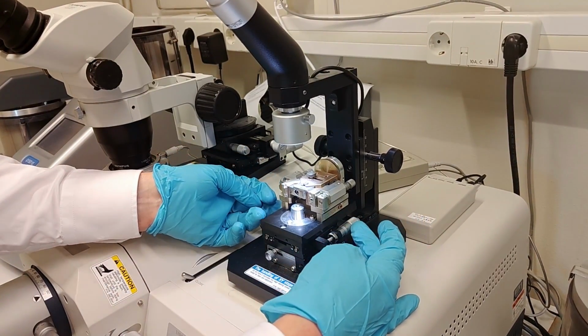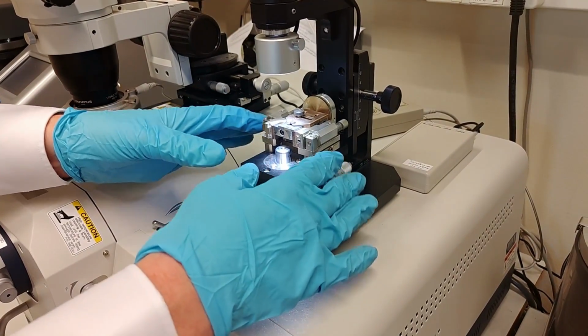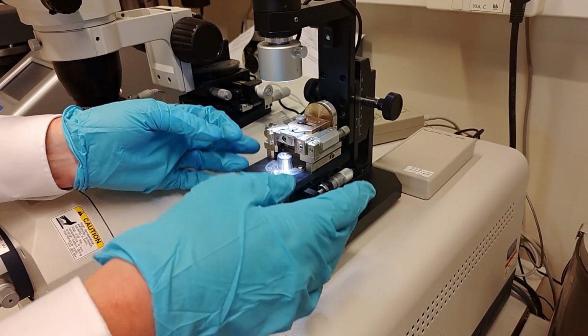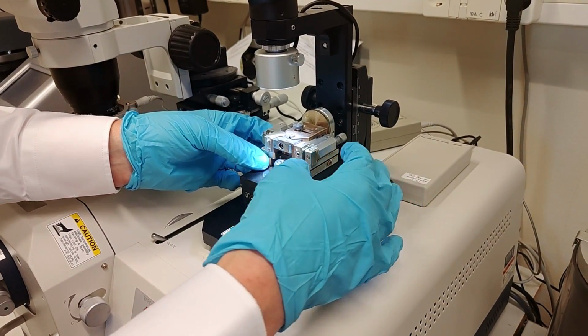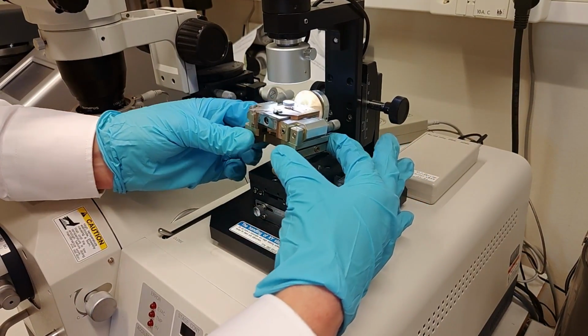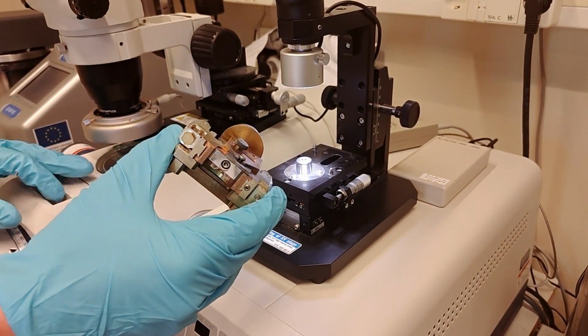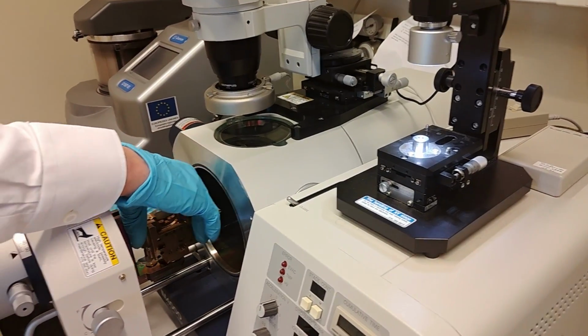These two screws on the bottom here, you should never touch. They are for calibration of the beam versus the whole thing here, so no users should play with this. So when I want to move this, I shall detach it. Take hold around the bottom part here, because it's very easy to touch the screws by accident and then you change everything.